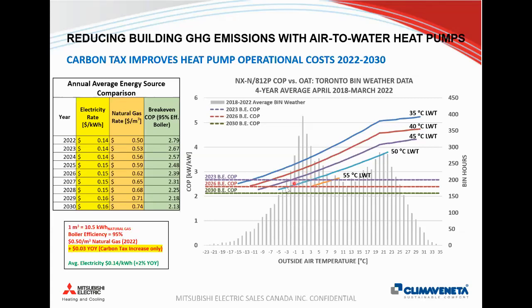And then below -3, we might be spending a little bit more money to run the heat pump, but we need to look at it through the average of the year, and it should balance out. But what I want to illustrate here is that over time, between 2023 and 2030, as we apply the carbon tax portion and a little bit of inflation for electricity, the minimum COP that we need to be cost neutral keeps getting lower and lower. So if we look to 2030, even if we're using a 50-degree supply temperature again, our COP is above the 2030 break-even line. So it's always going to be more economical to operate.